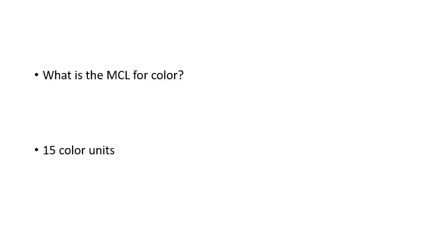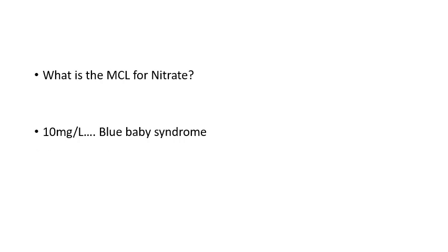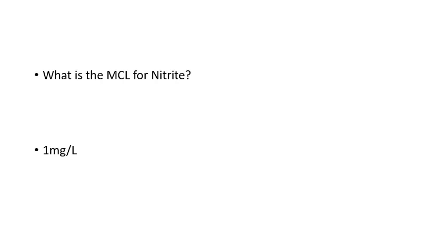What is the MCL for color? 15 color units, also a secondary standard. What is the MCL for nitrate? For nitrate, 10 milligrams per liter. What is the MCL for nitrite? The MCL for nitrite is 1 milligram per liter.